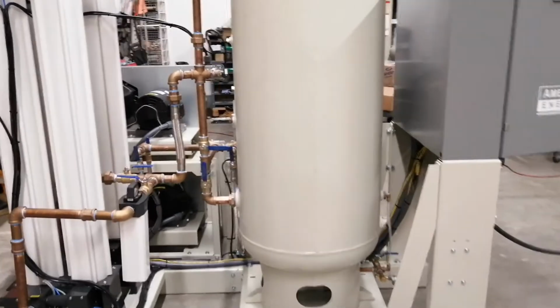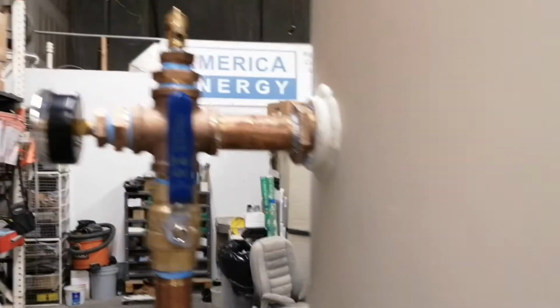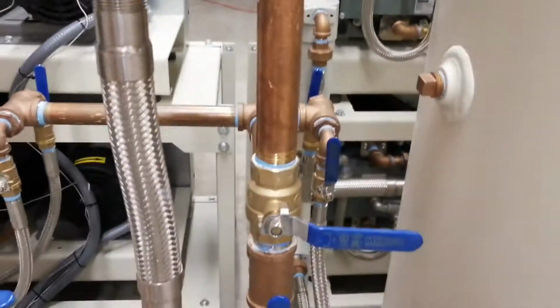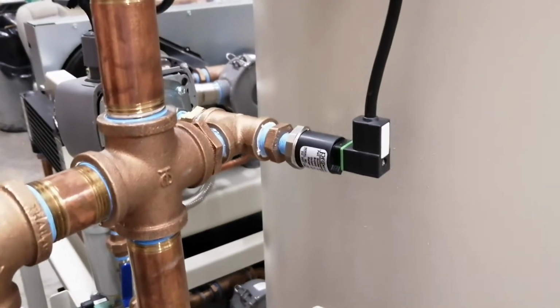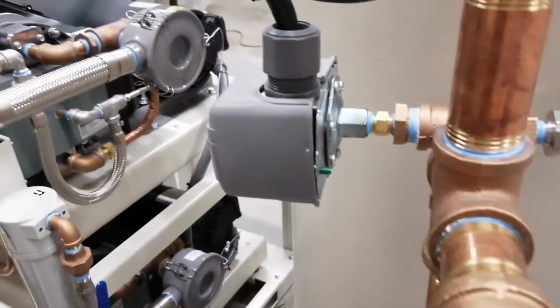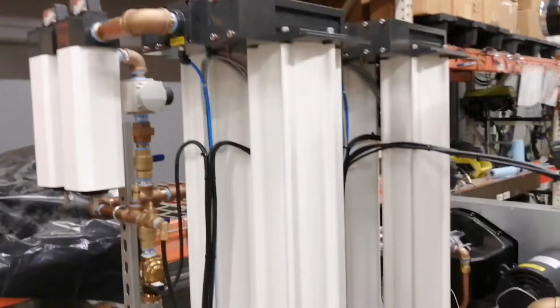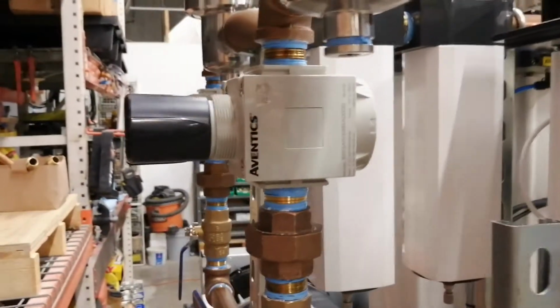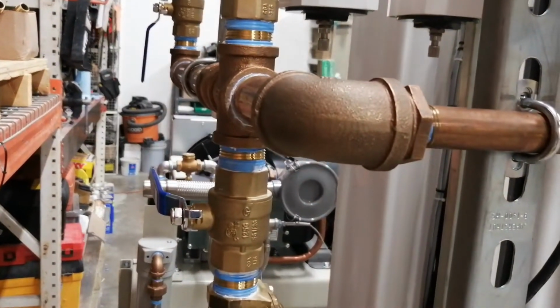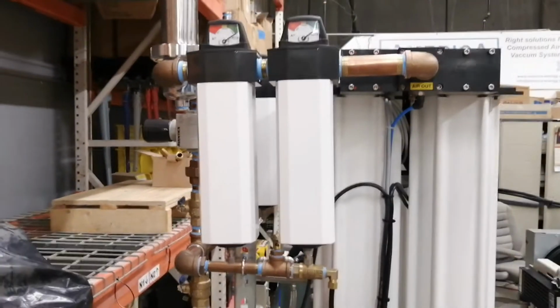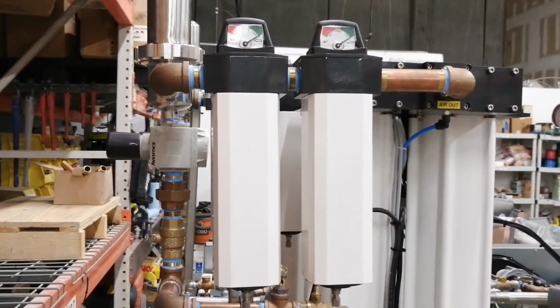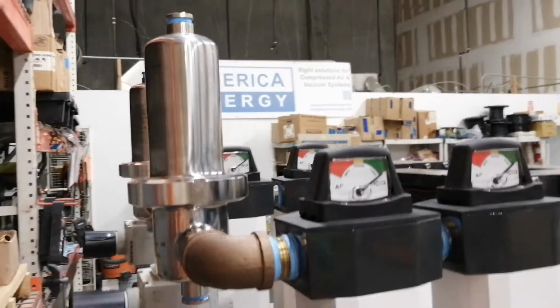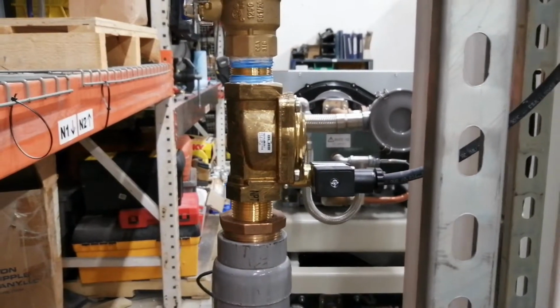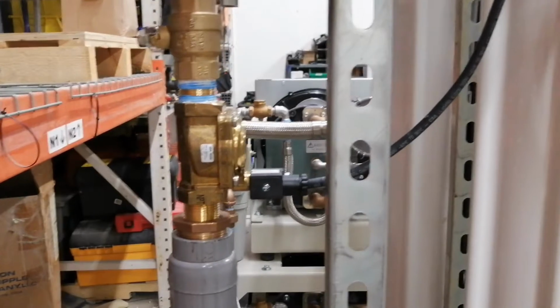The air treatment module is composed of the air receiver with inlet valve, discharge valve, safety valve, gauge, the bypass valve, pressure sensor to report the pressure over the HMI, a backup pressure switch, and the air treatment module with dual desiccant dryers with pre and post filter, pressure regulator, valve. In some cases, we can make it with an additional coalescing filter and an active carbon filter, a sterile filter, and also a solenoid valve to close air in case of any issue with CO or dew point, just for a special application.